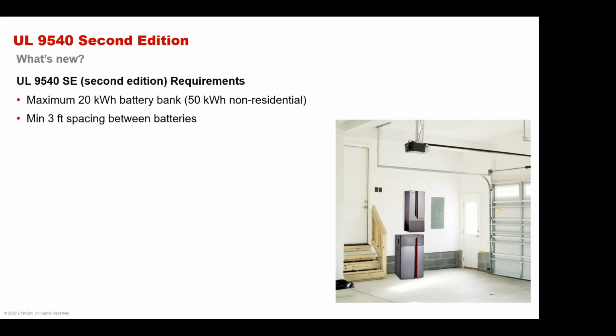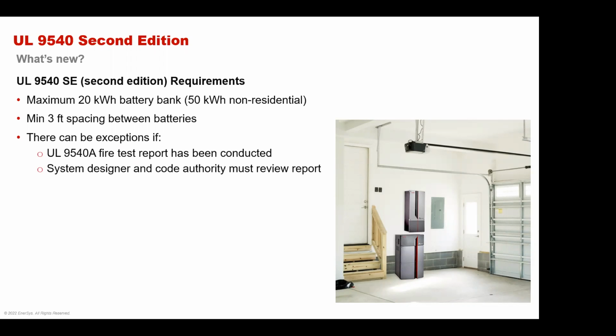So now there can be an exception, but it's going to require this UL 9540A fire test report. They're going to take that report, and as I said in the previous slide, the system designer and the code authority are going to review the report. They're going to determine if the 20 kWh and 3 foot spacing limits can be exceeded.